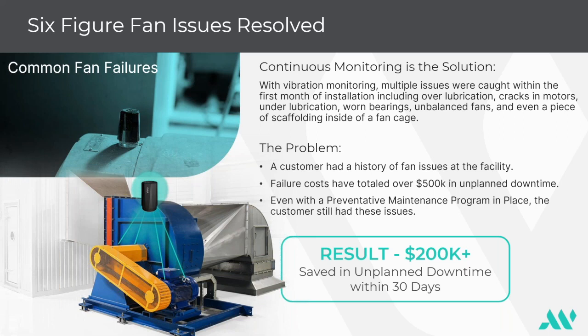They had a preventative maintenance program, and what that relied on was pretty much just a lubrication program where they came in and did routine lubrication. That alone caused over lubrication issues and even under lubrication issues, because the program really wasn't followed how it was implemented. I think it had been put in place 5 years prior, and that person left the company.